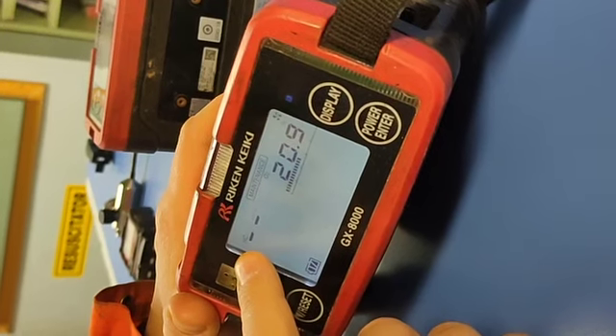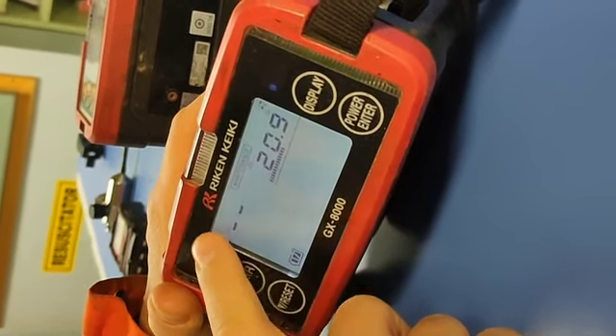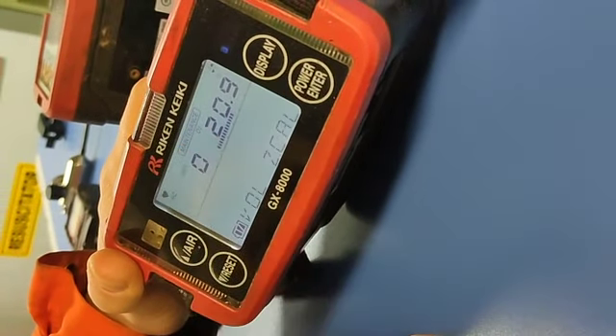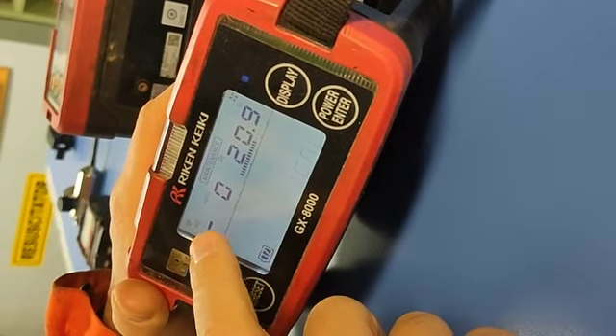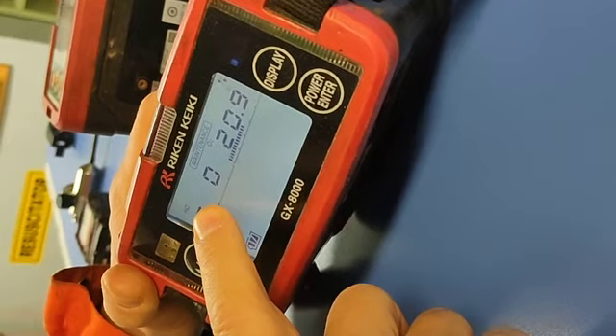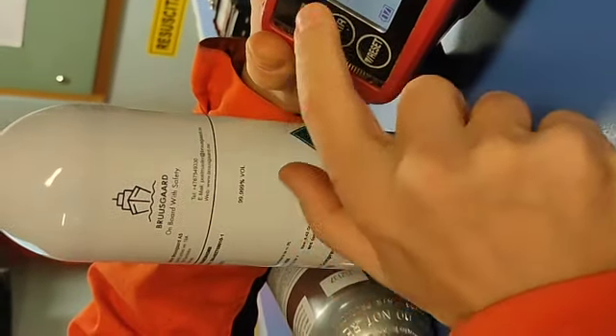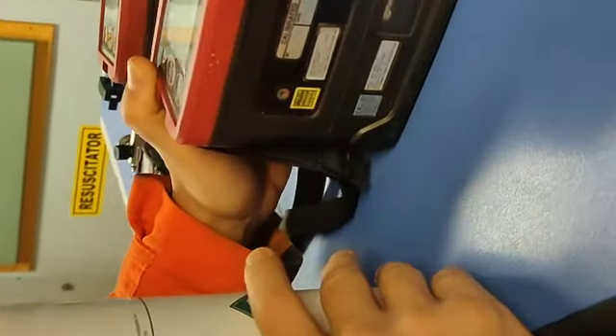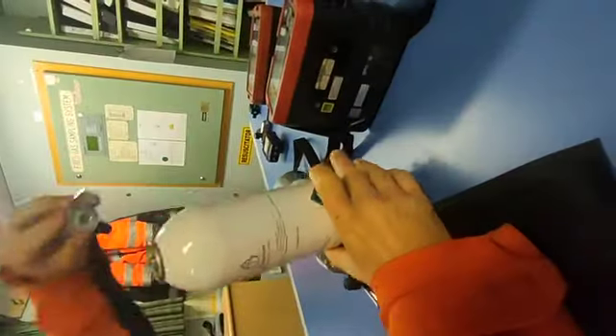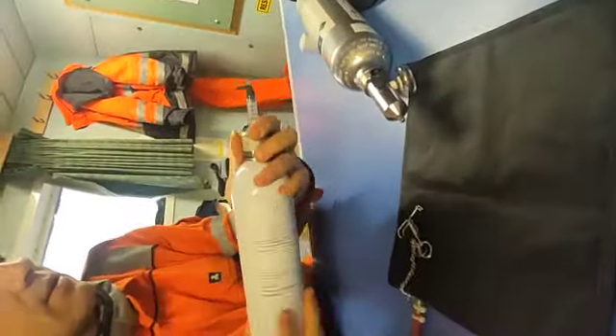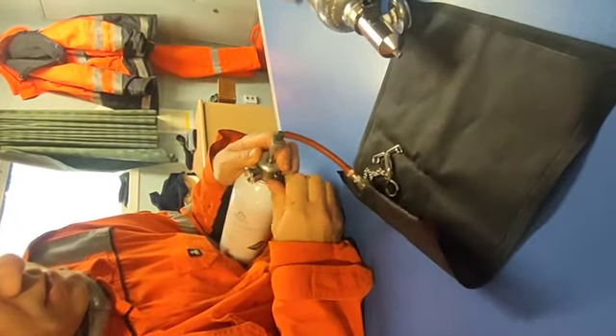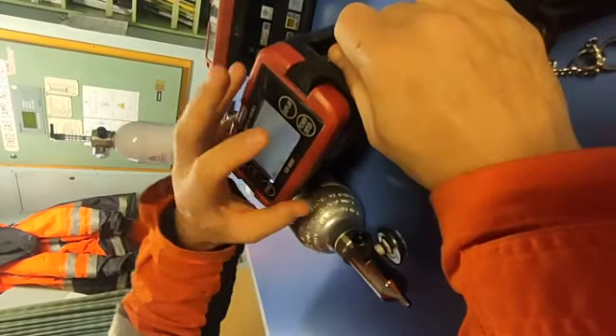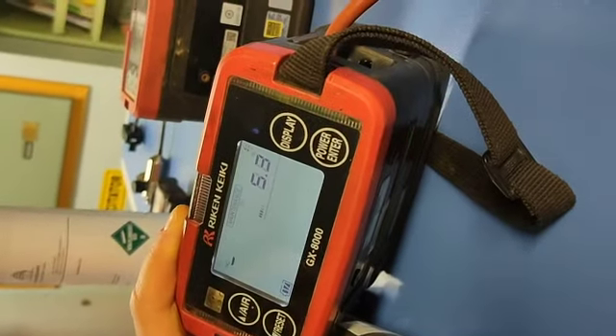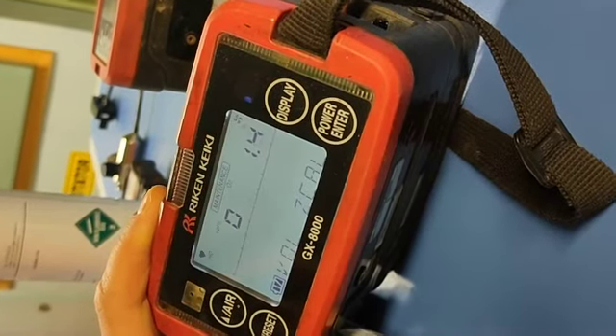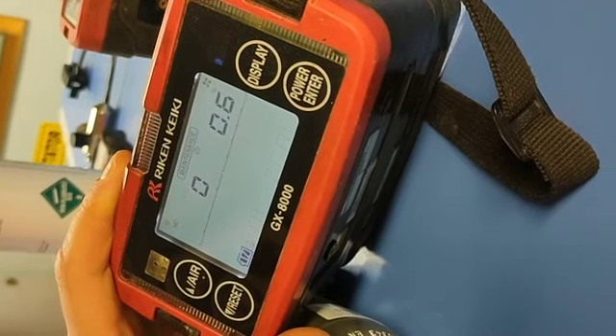Here in this menu appears also hydrocarbon percentage per volume. This sensor is also zeroing here together with the oxygen. This sensor we are using in inert atmosphere, so this is the proper gas to use when we zero the hydrocarbon percentage per volume sensor. This bottle is different, so we have a different reducer. We just apply one time enter and we will see the oxygen coming to zero, and of course it will zero also our hydrocarbon percentage per volume sensor.